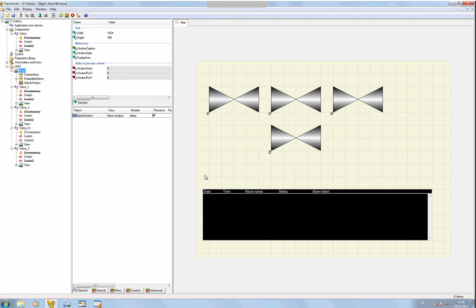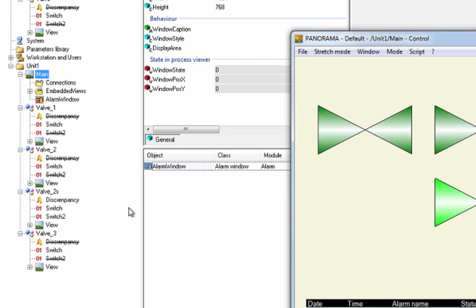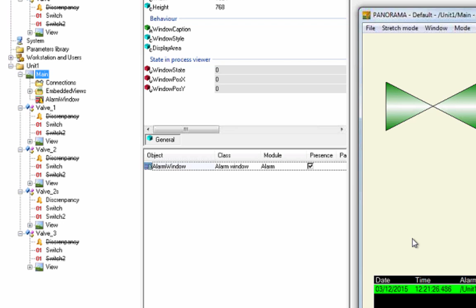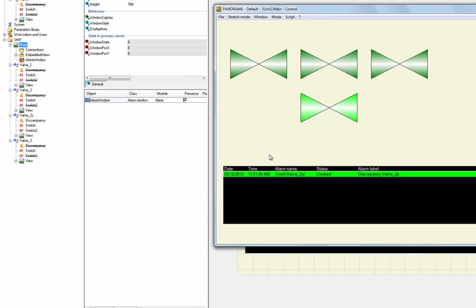Because the default simulated value for all variables is 0, my 2 switches have produced the discrepancy alarm. If I want to change this, I can change the status of my switch number 1 on this valve number 4, which produces the alarm clearance, and I can now acknowledge it. So as you can see, very quickly, we now have the possibility to create 2 kinds of valve, and the benefit of the components is saving time and increasing reliability, because these components are now errorless.